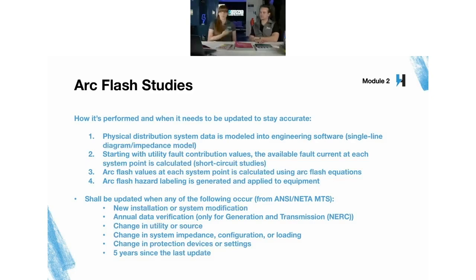into each location, the short circuit study that we talked about, which is required for the arc flash. Right. That's a major component in the calculations for an arc flash study. So you have to do the short circuit first, and then you can do the arc flash analysis for the incident energy analysis. And then that way you can get the potential available incident energy for each location in your system. So each means of disconnect, anything that's going to be likely to require examination, adjustment, servicing, or maintenance while energized per 70E and the National Electrical Code.